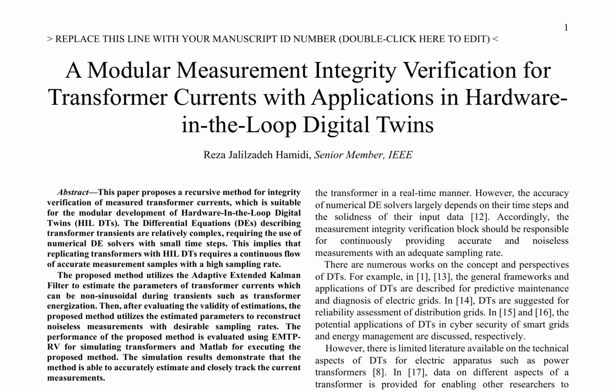The proposed method for integrity verification of measured transformer currents is suitable for the modular development of hardware-in-the-loop digital twins, HIL DTs. It utilizes the Adaptive Extended Kalman Filter to estimate the parameters of transformer currents, which can be non-sinusoidal during transients such as transformer energization. The method is evaluated using EMTP-RV for simulating transformers and Matlab for executing the proposed method.